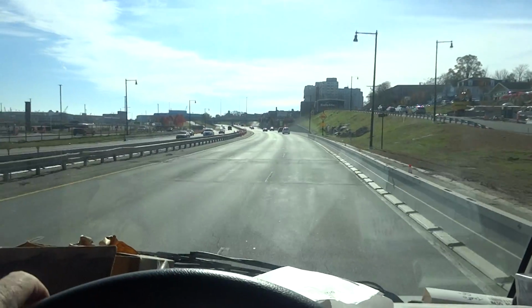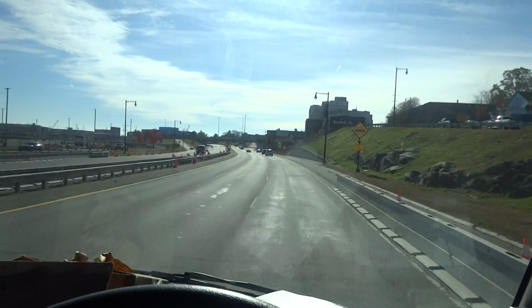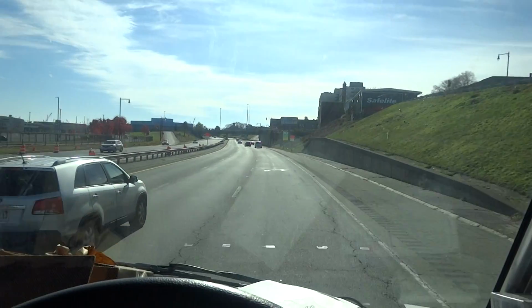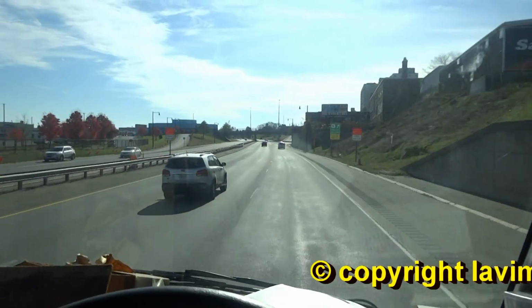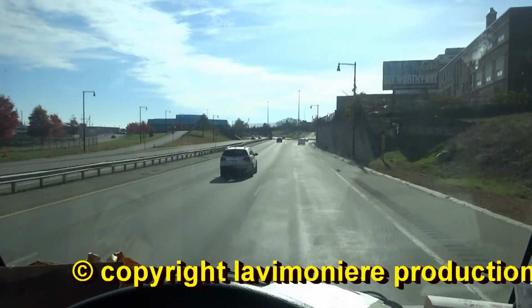Morning guys, November 15th, 2023. Today I got a call for a guy's got a gas boiler. He thinks that the damper control on the flue pipe's bad.